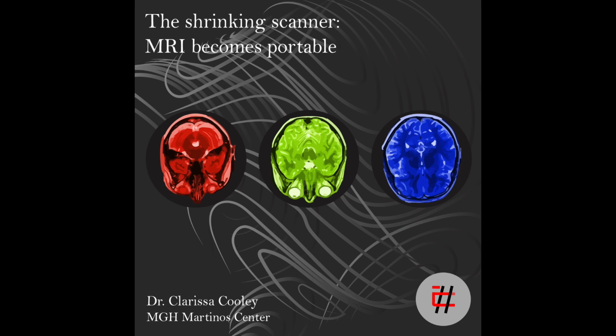And why do conventional scanners need to be so large and expensive? The reason they're so large is to make a really strong uniform field that is body sized. You need a really big magnet. The conventional scanners have a very uniform field, with only a few parts per million variation. To achieve this very high field strength that's very homogeneous, they use superconducting magnets with liquid helium cooling, which also adds to the cost and the complexity.